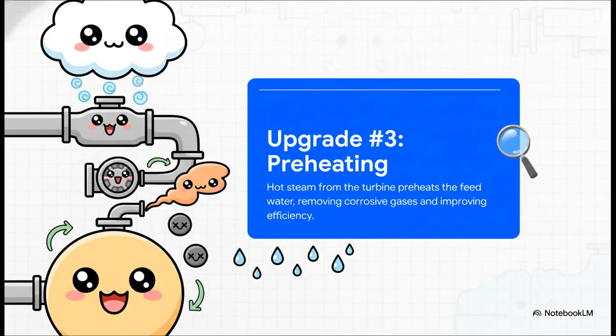This next trick, preheating, solves two problems at once. Before the water even makes it to the boiler, it's preheated using a little bit of hot steam siphoned off from the turbine. This recycles heat, which improves efficiency for sure, but it also helps get rid of dissolved gases like air from the water, and those gases can cause corrosion that damages the expensive boiler over time.